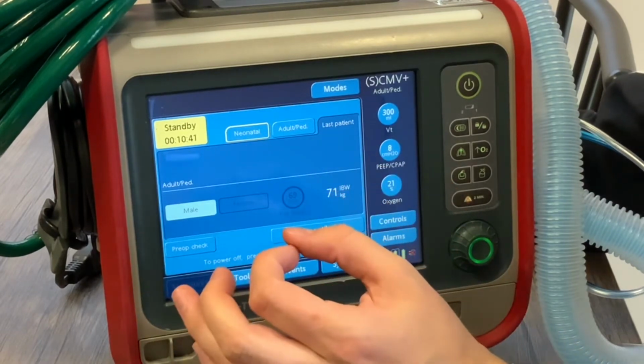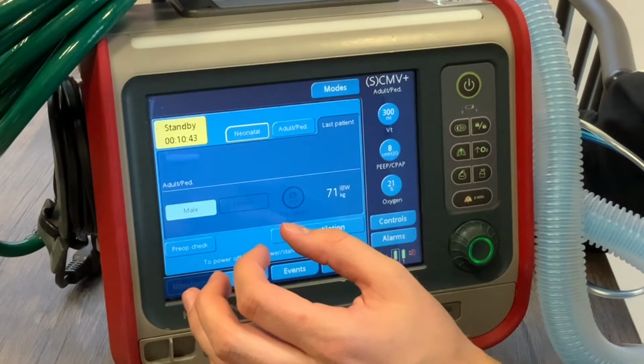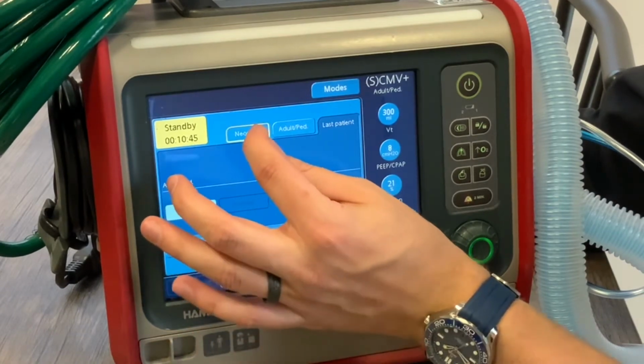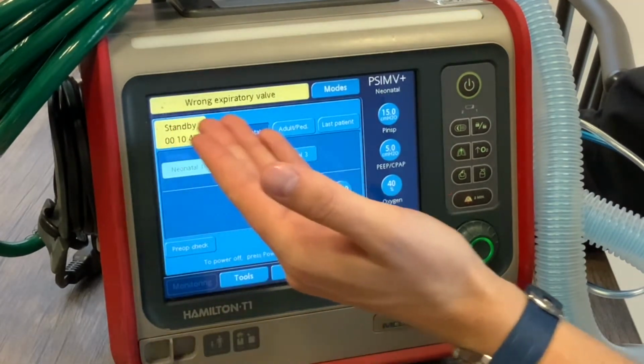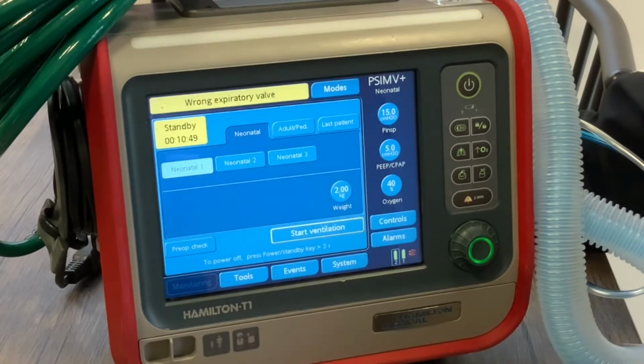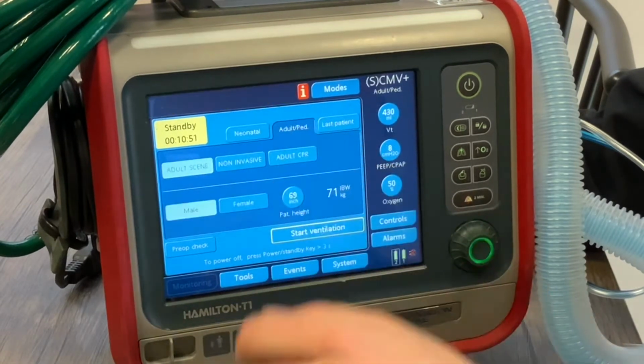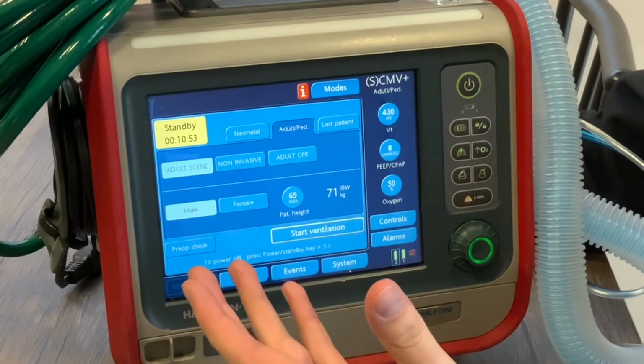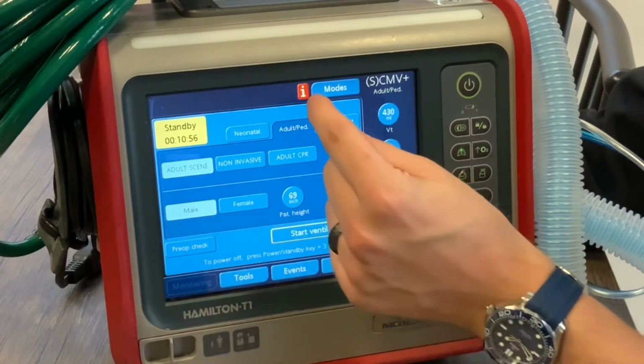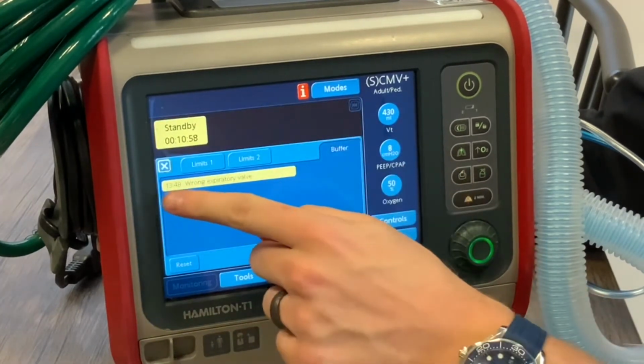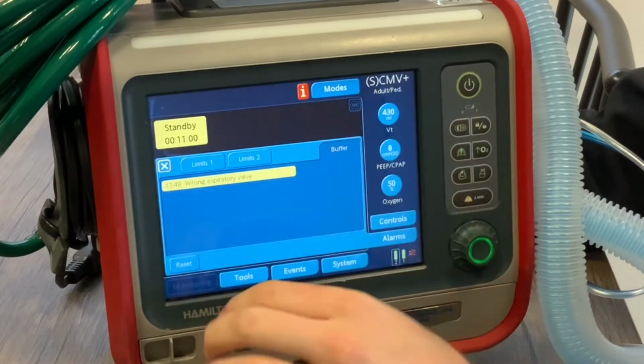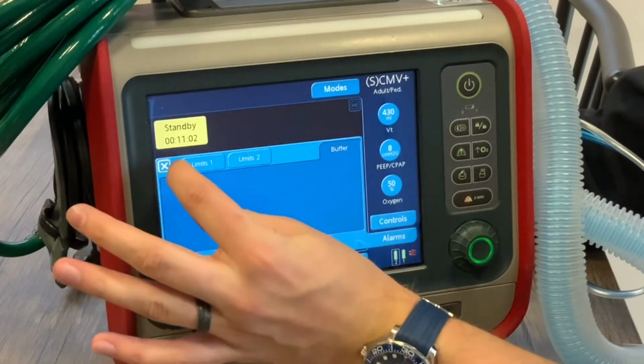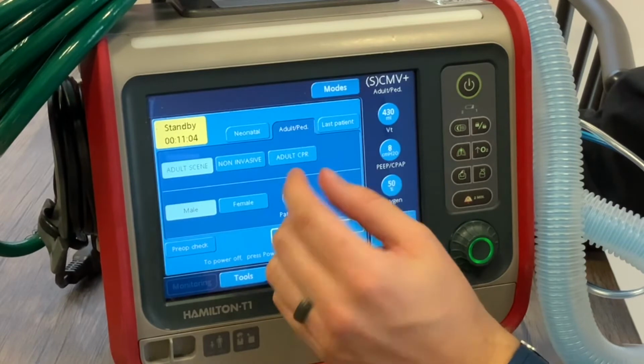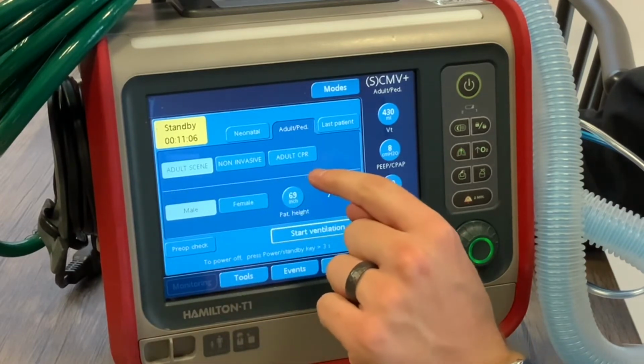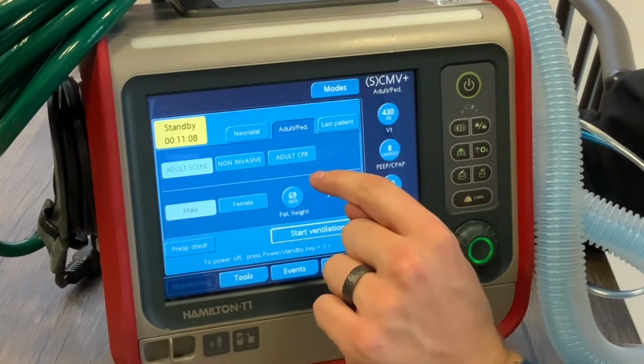When the adult pediatric expiratory valve is on, and we select neonatal mode, it brings us this alarm, wrong expiratory valve. We simply need to select adult pediatric, and that will get rid of the alarm. Just as always, if we click the I, it shows us wrong expiratory valve, that alarm is no longer active, we can reset. Under adult peds, we have the 3 standard modes for the Hamilton.